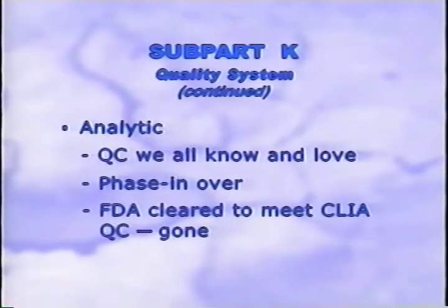The analytic section contains the quality control requirements that we all know and love. These requirements now apply to all non-waived testing. The phase-in is over. Also, the references to FDA cleared as meeting the CLIA requirements for quality control have been removed. Quality assessment has been dispersed throughout the regulation with general laboratory systems, pre-analytic, analytic, and post-analytic each having an assessment piece.